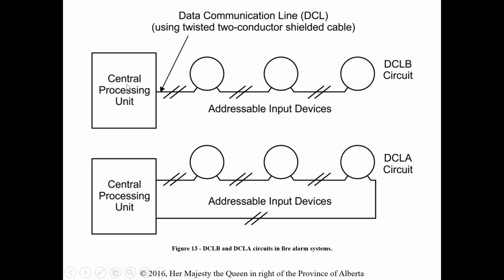The advantage to an addressable system is when I go and scroll through the display, I can actually see which device is the one that's having the issue. So as far as troubleshooting, this is a huge advantage, obviously. We can still have our B circuit and our A again. With A, we can see here's our loop back to the panel. But when these are all addressable, it's a huge advantage for troubleshooting, in my opinion.